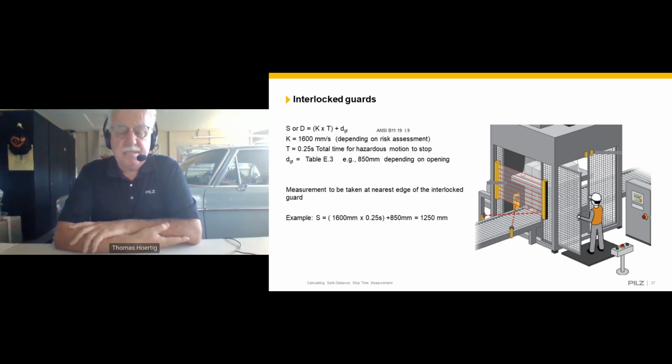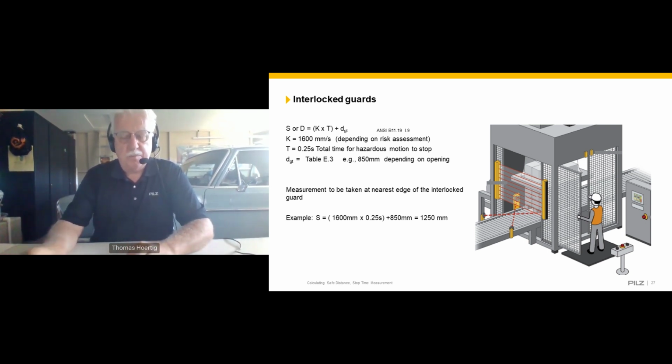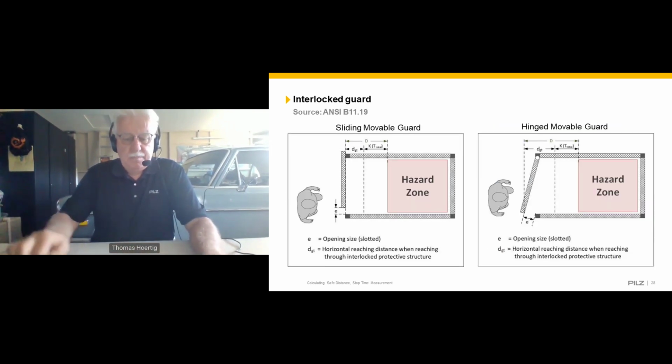What can be done in these cases is you use an interlocked safety door switch with guard locking that would keep the door closed until your guard locking switch, and by 0 speed standstill will allow you the door to open. Here out of ANSI B11.19, we have 2 examples here.